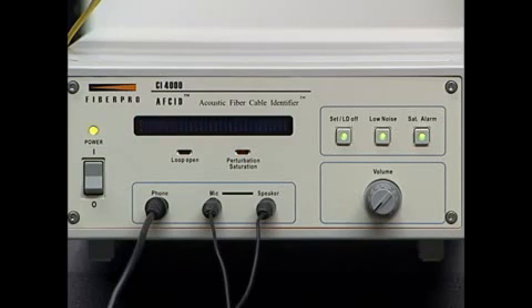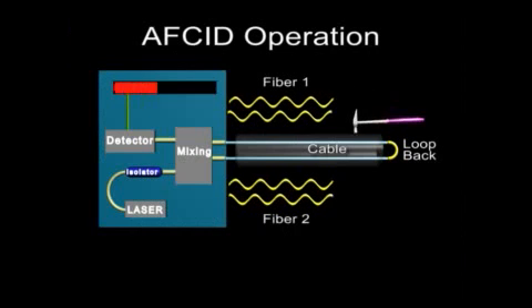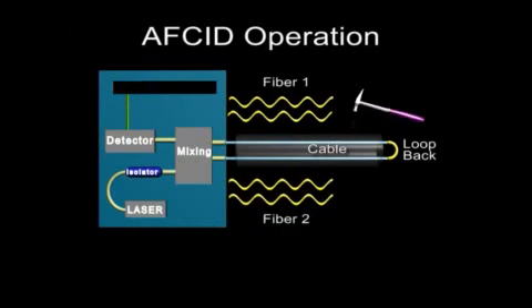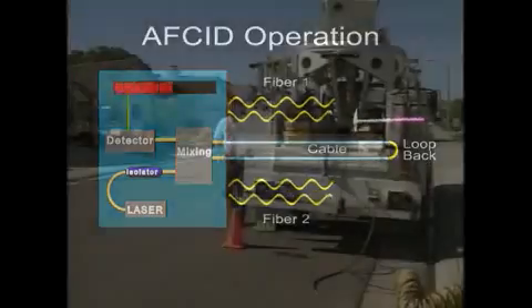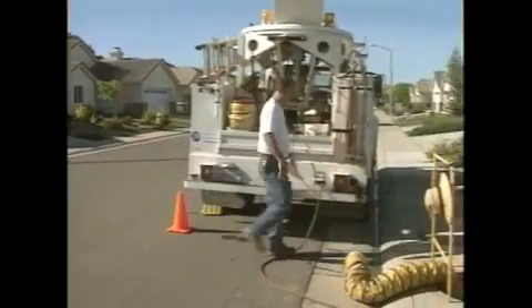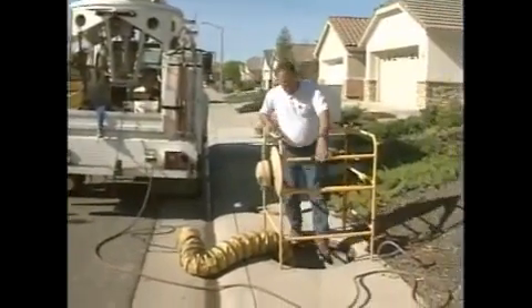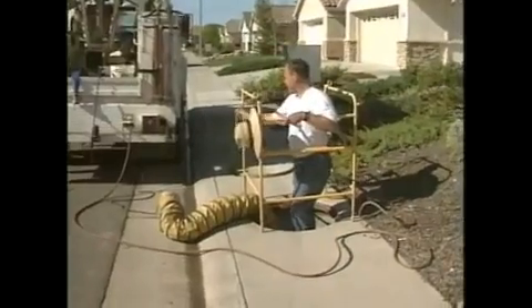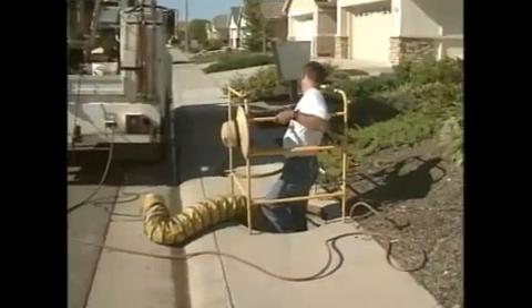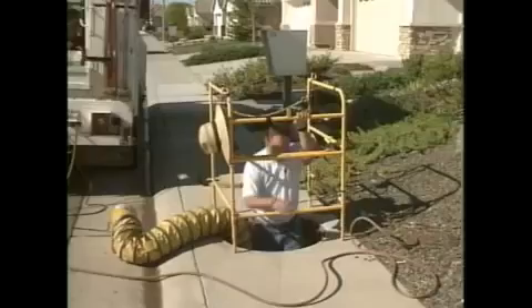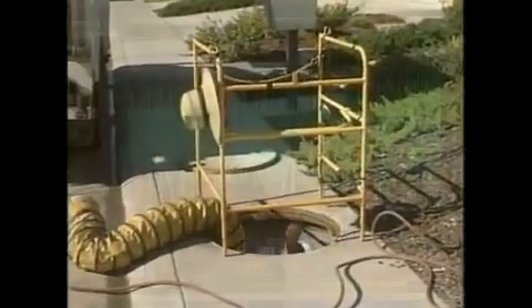A visual indication of the tapping sound will be displayed on the LED bar graph on the front panel of the instrument. The optical characteristics of the interferometer dictate that the cable will become less sensitive to mechanical tapping the closer you get to the loopback site, with zero sensitivity at the loopback point itself. When locating cables near the loopback, it is recommended to keep at least 1 kilometer of fiber distance away from the loopback and switch the noise reduction off to maximize sensitivity.